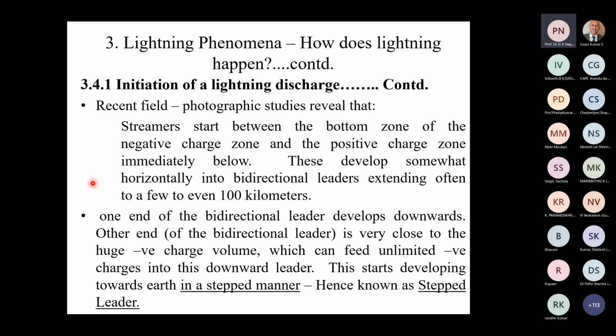So a streamer is where electrical discharge development is primarily due to the applied electric field and ionization by collision between electrons and neutral molecules. Once the current density in the streamers becomes very high, high temperatures develop, and thermal ionization becomes much more prominent than ionization by collision. This is known as a leader, which can develop by itself, providing the electric field is adequate for its propagation. That's the distinction between the streamer and the leader.